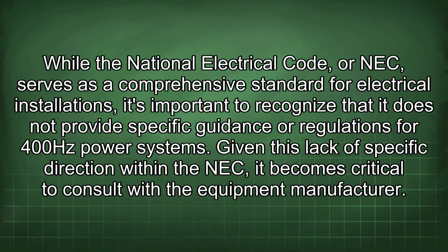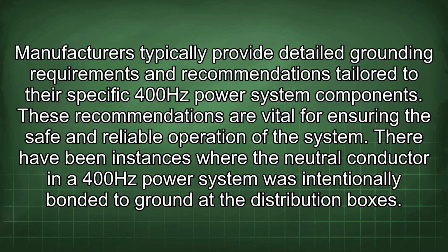While the National Electrical Code, or NEC, serves as a comprehensive standard for electrical installations, it's important to recognize that it does not provide specific guidance or regulations for 400 Hz power systems. Given this lack of specific direction within the NEC, it becomes critical to consult with the equipment manufacturer. Manufacturers typically provide detailed grounding requirements and recommendations tailored to their specific 400 Hz power system components. These recommendations are vital for ensuring the safe and reliable operation of the system.